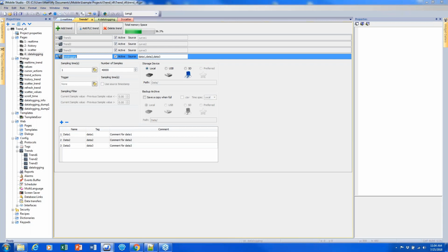There were a couple of questions about recipes and exporting recipes, doing some editing, and then what would be the way to modify the recipes and re-import them into JMobile. The fact that it's a CSV file is a little bit challenging. It can be opened in Excel. The key is, if you save it as a CSV, Excel kind of modifies the file. But there's an option in Excel to save as a CSV in UTF format, which is a kind of Unicode, and in that case, that file is preserved as it was and can be used as an import to bring in the edited recipe.